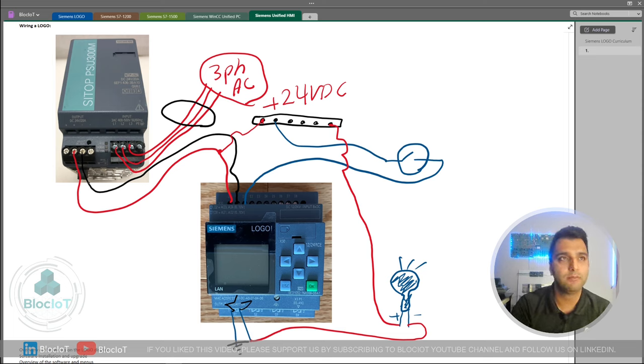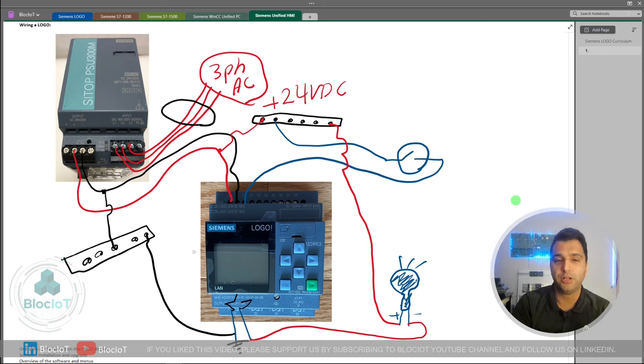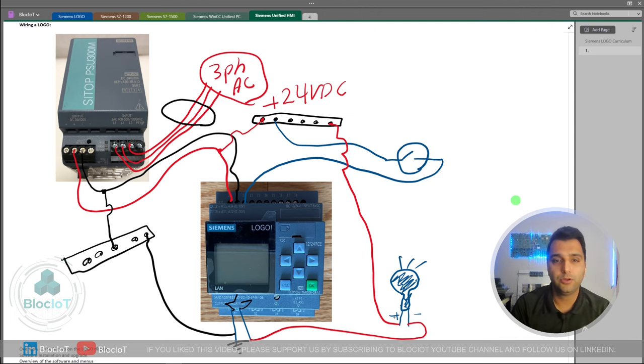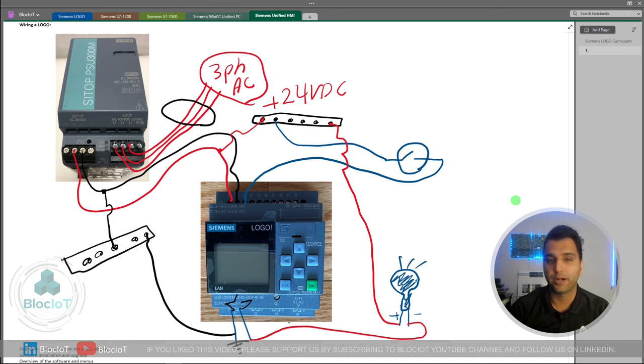In your program you control the status of this relay switch to be on or off. If you have a DC output instead of a relay output, you don't need to connect your actuator to the power supply directly, because a DC output on the Logo or any PLC means you will get a 24-volt DC voltage on the output pin when you set it to one in your program.